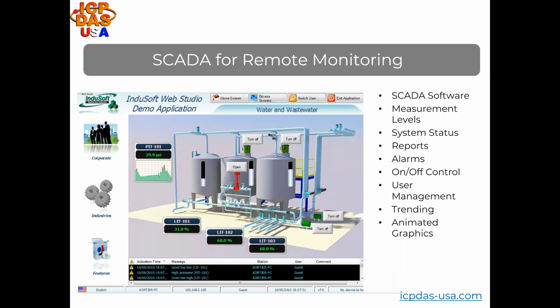There are buttons that you can click to remotely close the valves and turn off pumps. Trend graphs show the status of tank levels over time. Customized reports are getting emailed out at scheduled times. The alarm window at the bottom shows when levels are out of range and also shows high pressure warnings. Animated graphics show a realistic visualization of the system status.